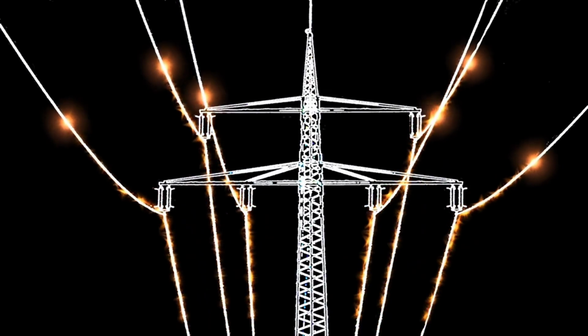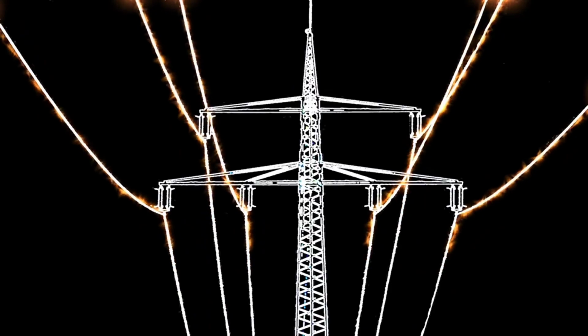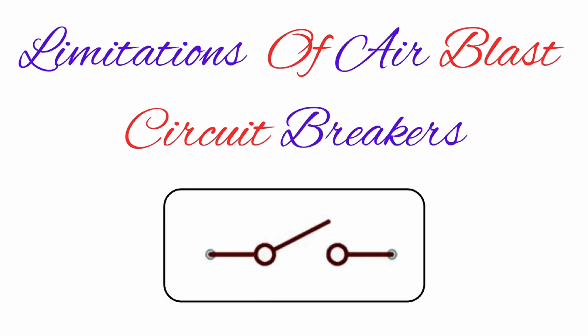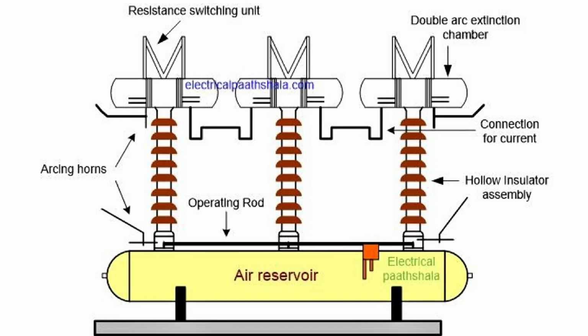Having known the areas of application of air blast circuit breakers, what are the limitations of using it in power systems? While they offer several advantages, ABCBs also have some significant disadvantages that need to be considered. One of the primary concerns with ABCBs is that they require a compressed air pump system to operate. This means that the compressed air system needs to be maintained regularly to ensure reliable operation of the circuit breaker.